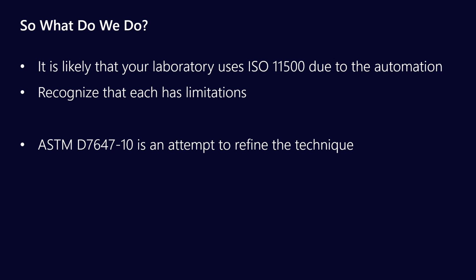So what does that mean for us as recipients of used oil analysis reports? It's 99% probable that your laboratory is using the ISO 11500 test — the automated laser light test — because your local laboratory is probably processing thousands of samples per day and simply doesn't have the time to do a manual test. This is not to say the test is wrong, but it is imperfect. We can also look at ASTM D7647, which is an attempt to refine the automated technique to account for water, air entrainment, and soft particles.